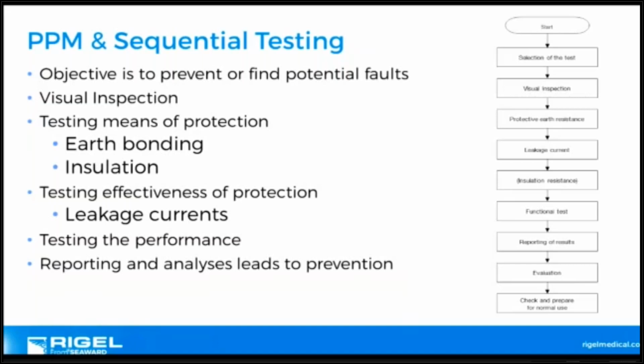too and record things. The recording in particular is another thing that is different from 60601, because the traceability is very important with 62353, and analyzing and comparing within 62353. So it's totally different in regards to what it expects the user to do. Also included is a functional check, so it actually measures the current within the device.